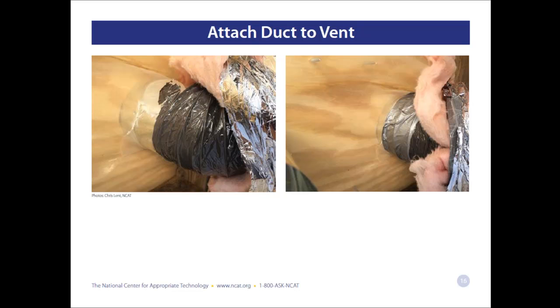And the way you attach these to the back of the vent hoods is you peel back the insulation from the flex duct, slide the flex duct over the back of the vent hood ductwork, and then use duct tape to air seal that. It's probably the only place on your farm where you'll actually be using duct tape in the way it's supposed to be used on ductwork. And that creates a nice air seal. And then it's not shown here, but you pull the insulation back over the ductwork and put a zip tie around it so it's nice and tight, and you have an air sealed insulated connection there.